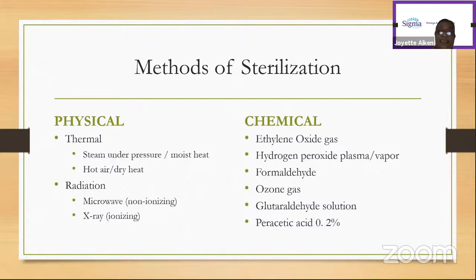For chemical sterilization, there is ethylene oxide gas, there is hydrogen peroxide plasma or vapor, there's formaldehyde, ozone gas, glutaraldehyde solution, and peracetic acid, 0.2%. The most common method of chemical sterilization that we use in our context is ethylene oxide gas. Glutaraldehyde or Cidex is also used, but primarily for high-level disinfection, although in the end, Mrs. Ford did tell you that it could be used as a chemical sterilant, which is so.